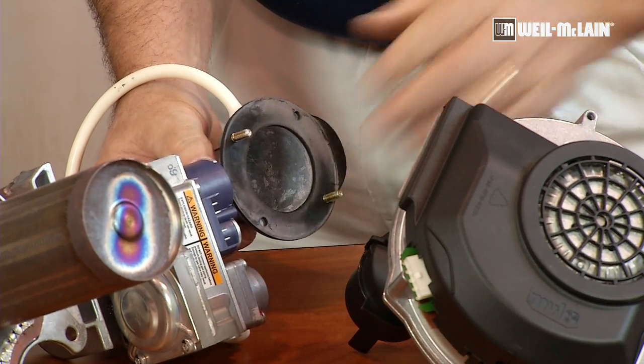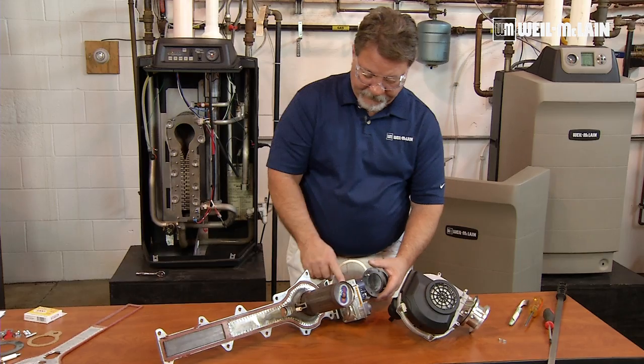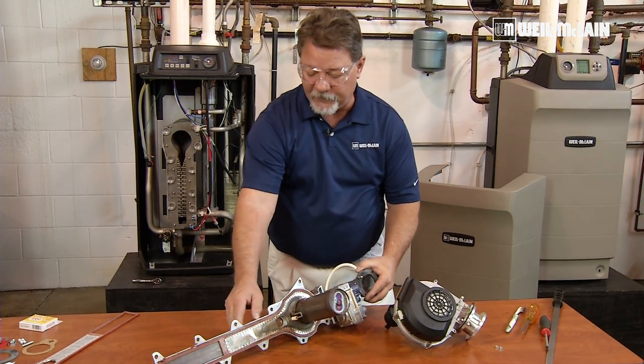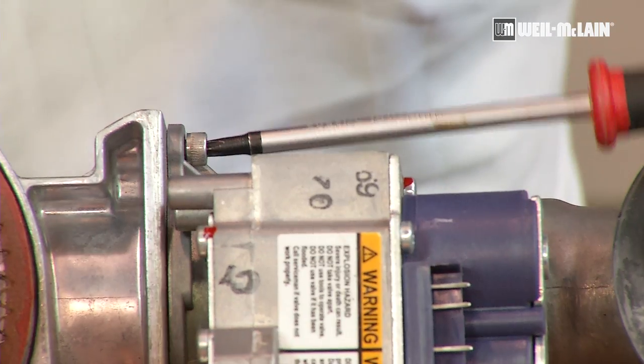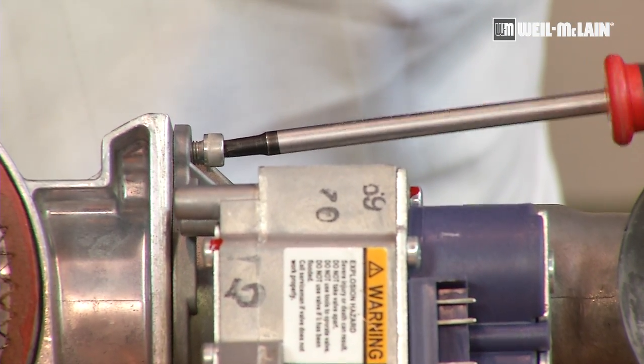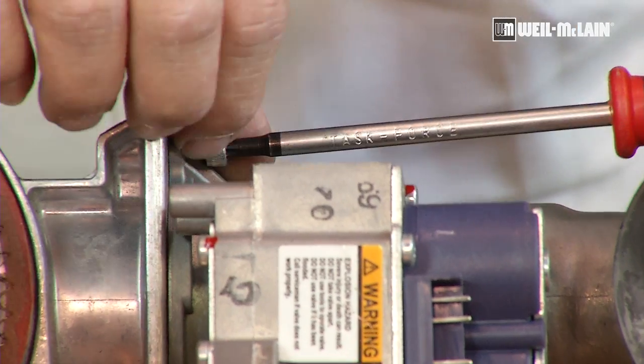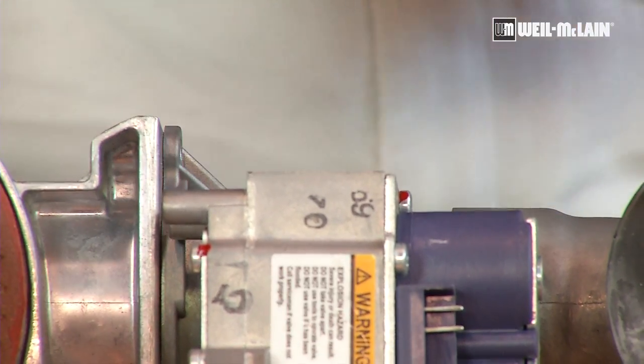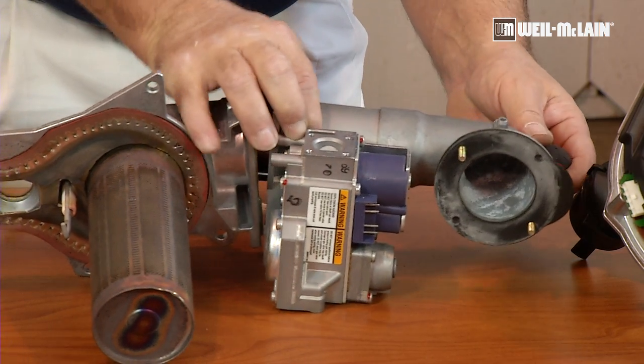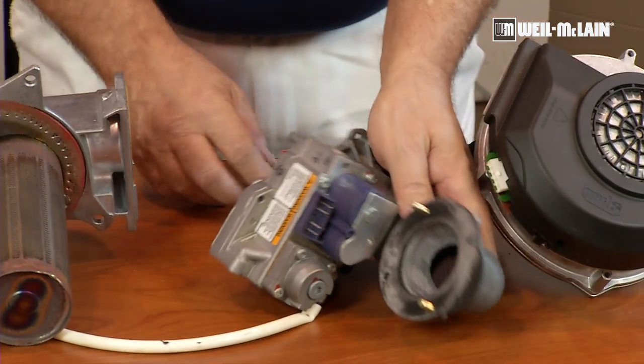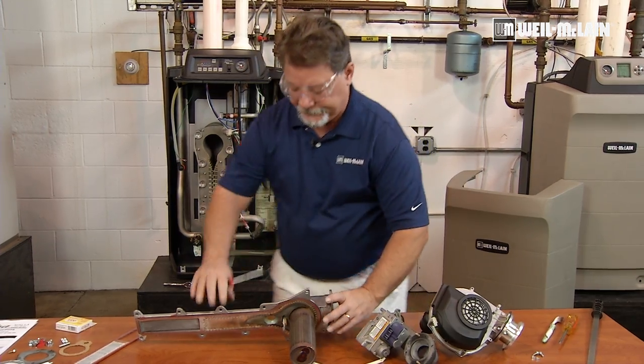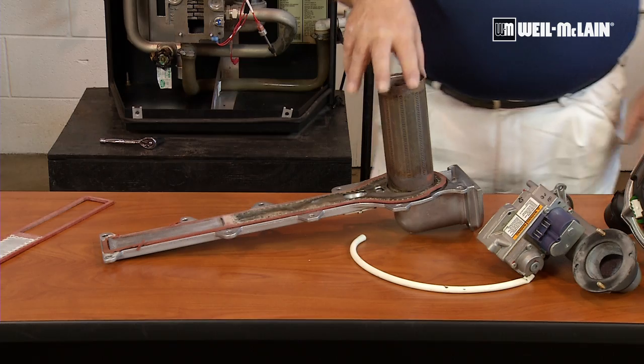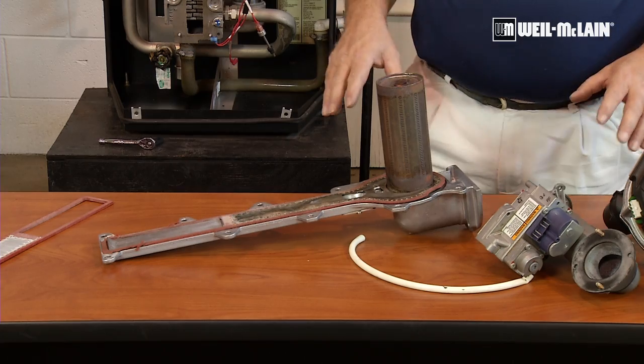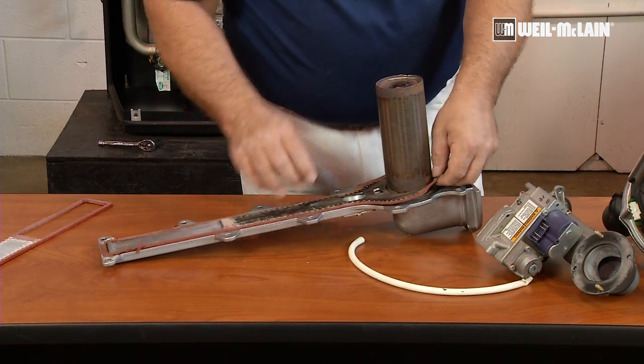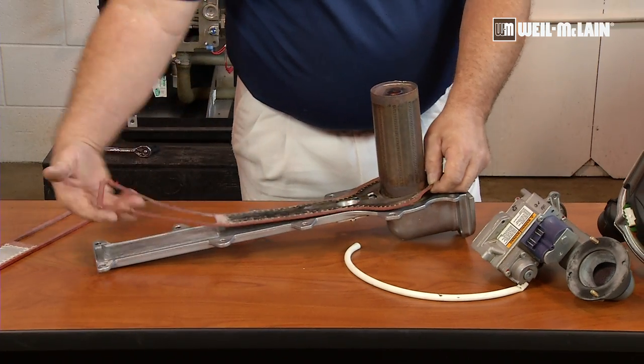The next piece that I'd like to remove is the venturi gas valve assembly from the front cover plate here. And to do that, there are two 25 Torx machine bolts that we're going to remove. We'll set that aside. Now I'm going to remove the igniter. The last step is going to be really our first service item. We're going to remove the insulation from the cover plate. That just simply pulls out.